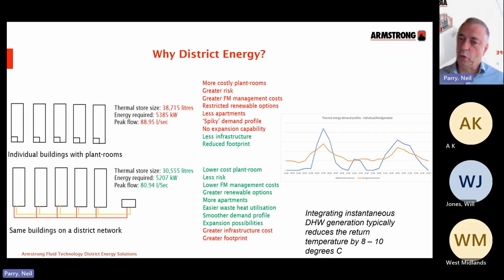You also obviously increase your base load, so you've got something for your renewable energy sources to go at, if you like, before you get to the peaking area, where a lot of that peak can, of course, be supplied from thermal storage that you're using your renewable energy to load prior to those peaks. So what you tend to find is your peaking energy sources tend to be more carbon intensive, and by amalgamating those loads, smoothing those peaks and troughs, you can reduce the requirement for that fast modulating energy source.